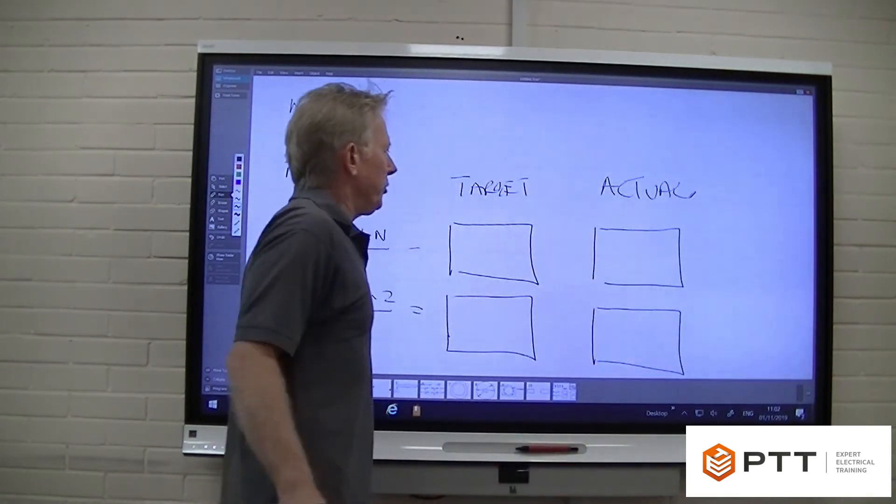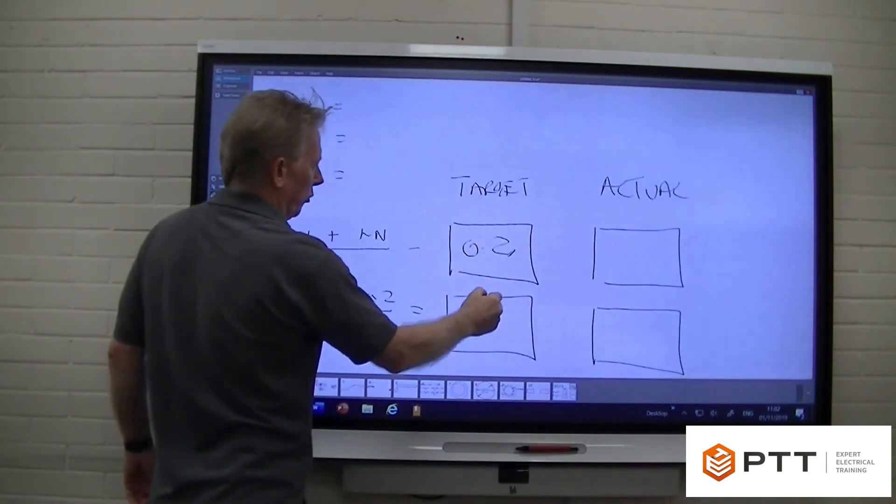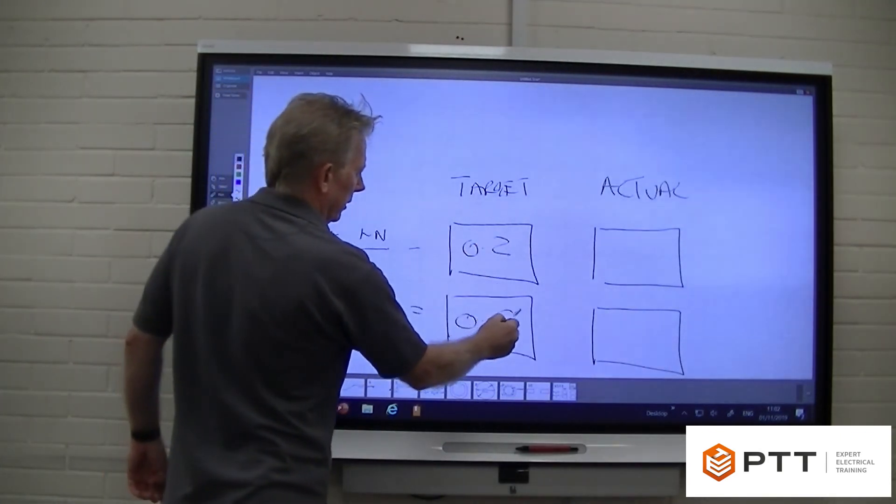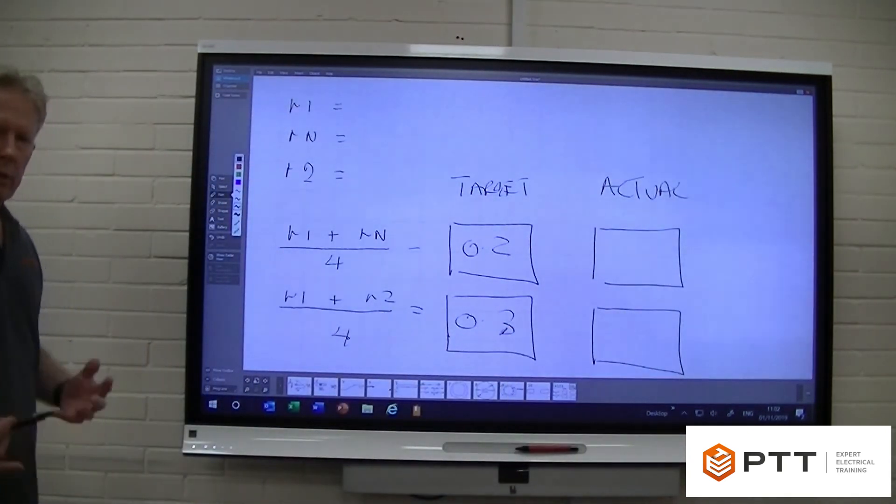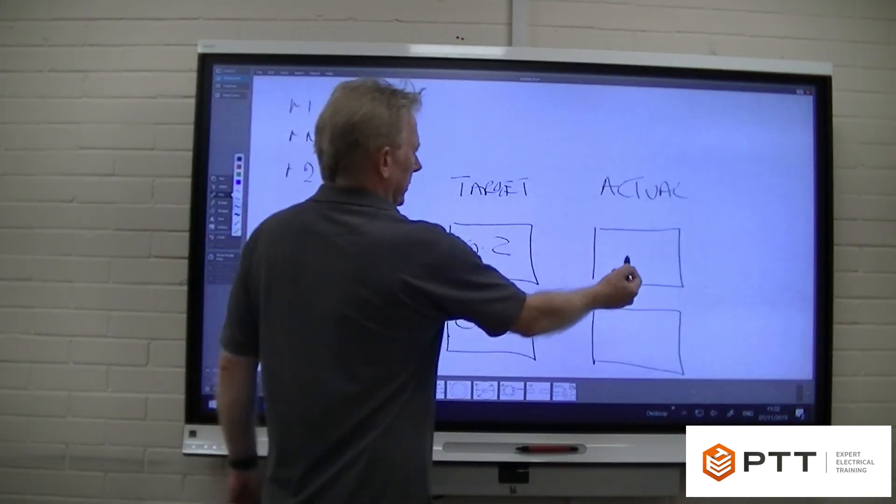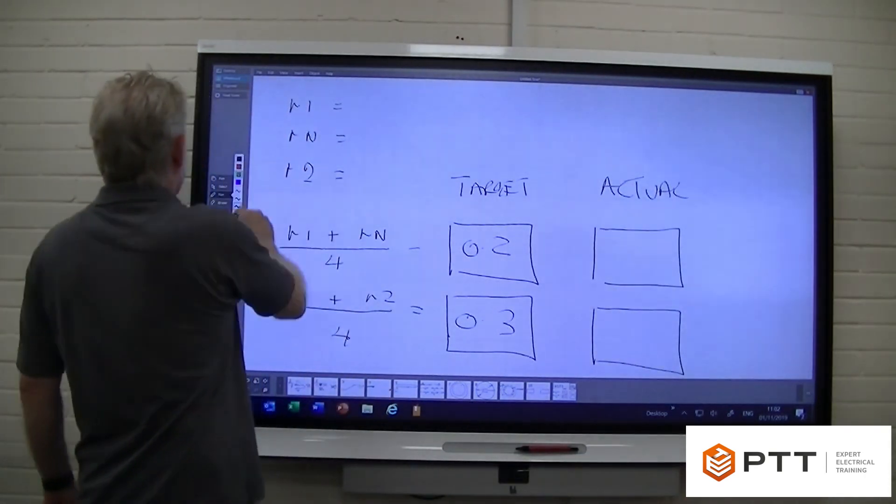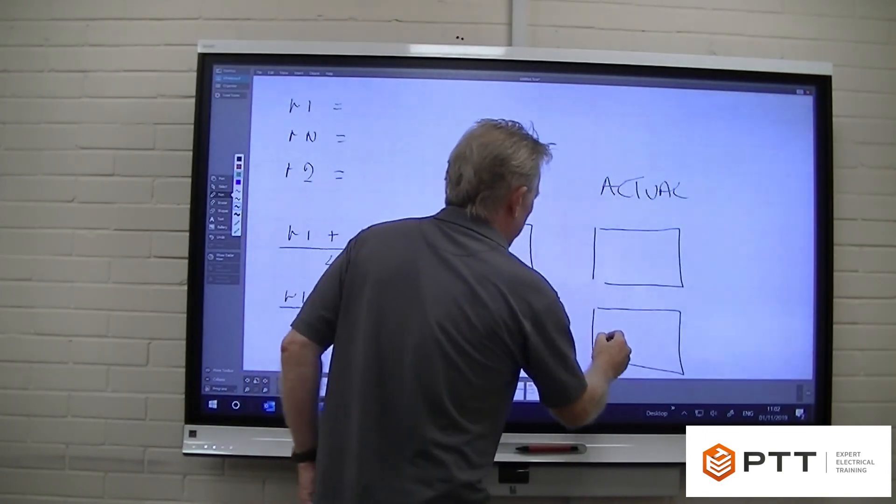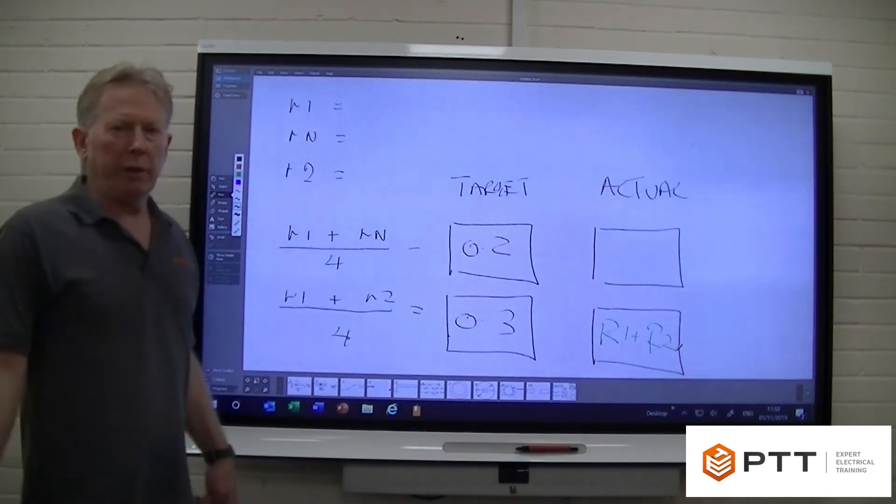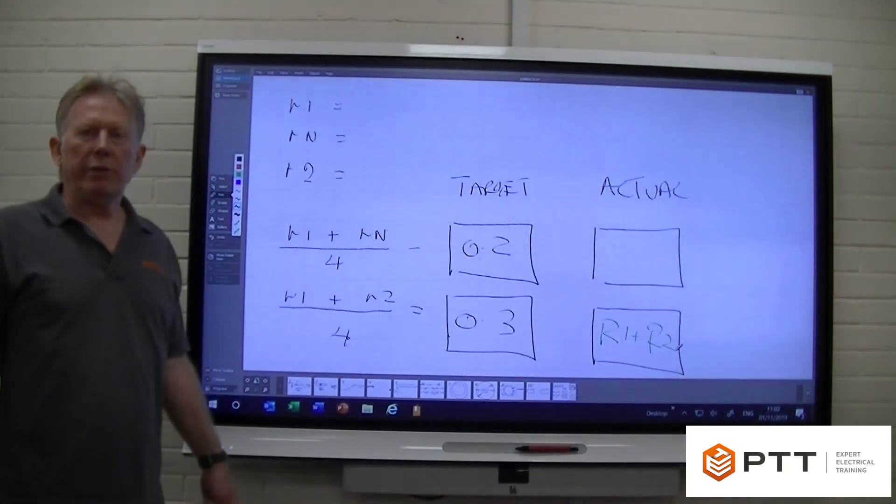So what we have here is the actual measurements. So we put our target figures in here, which were 0.2 and 0.3. We do our cross connections, and then we record our results. It's the result of this one here that actually becomes the r1 and r2 for the ring circuit.